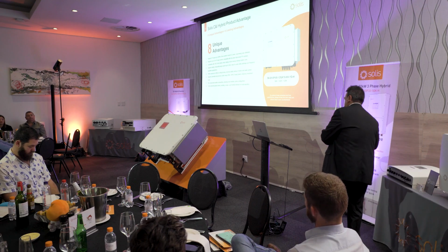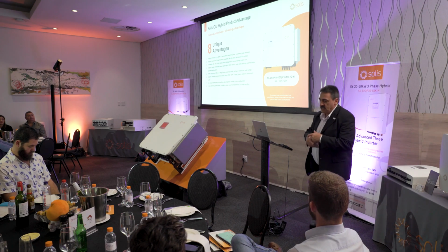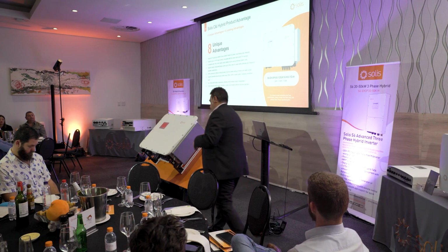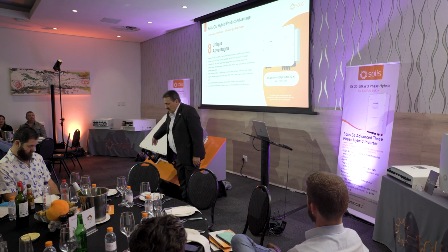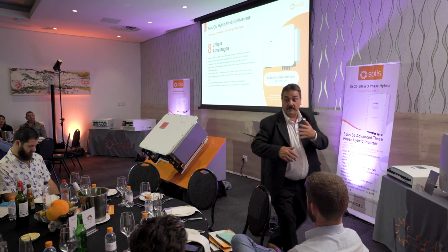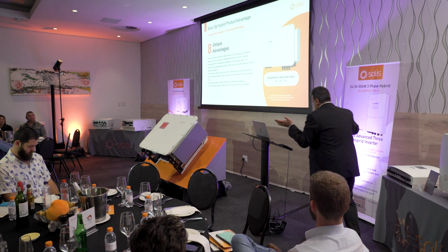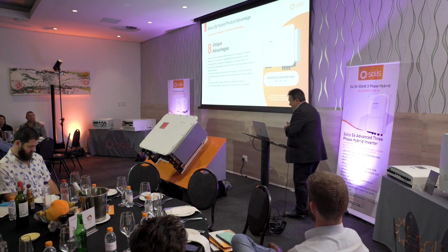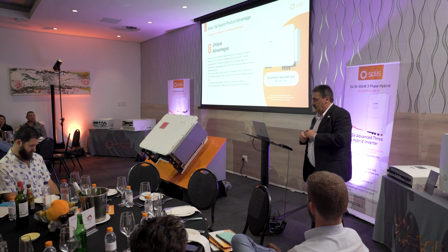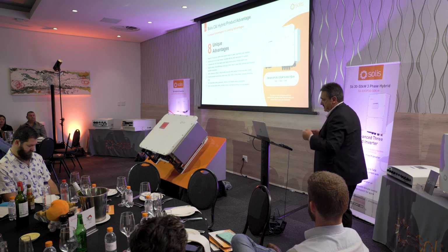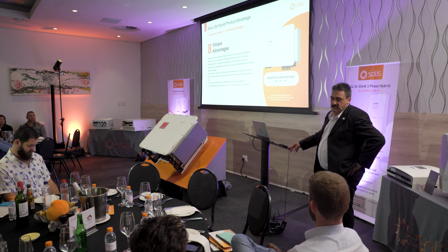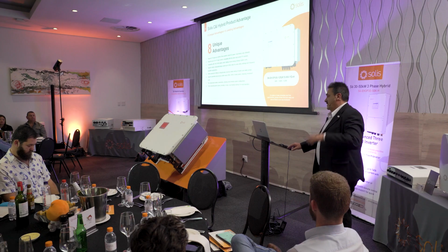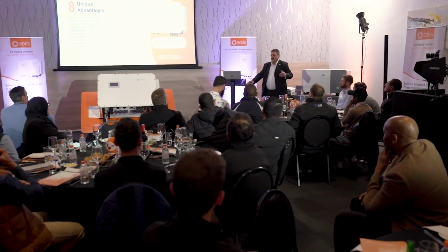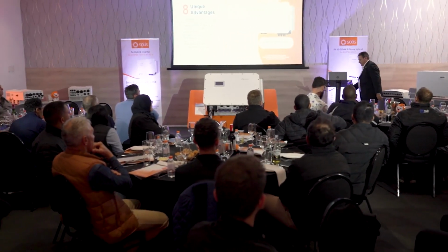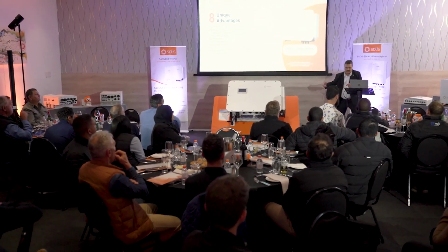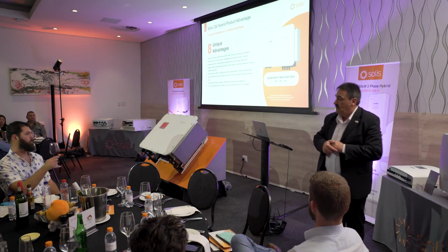People ask, why would you want to do that? Say you start off with a 125 kilowatt battery bank running through one port because your customer can't afford more yet - that's fine. But when it's time to upgrade, the guy who sold those batteries has moved on. Now your customer doesn't have to throw the old batteries away and buy a whole new pack - you can just add a second bank from another manufacturer.